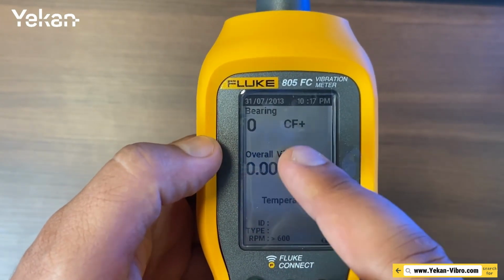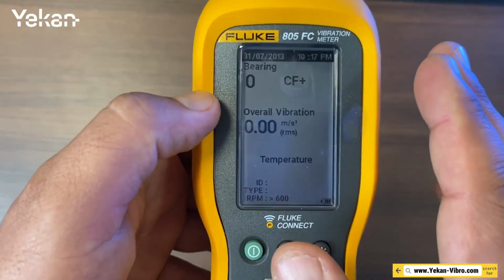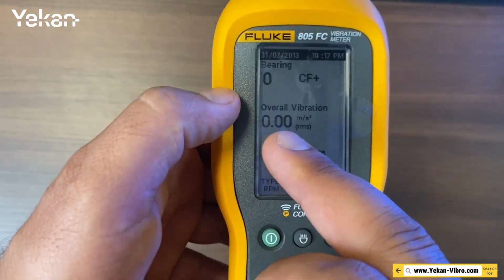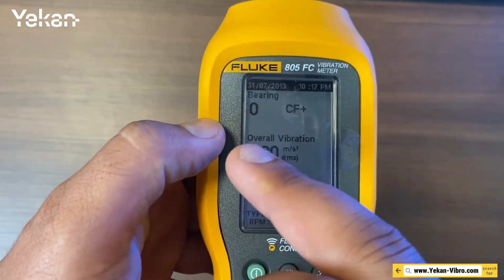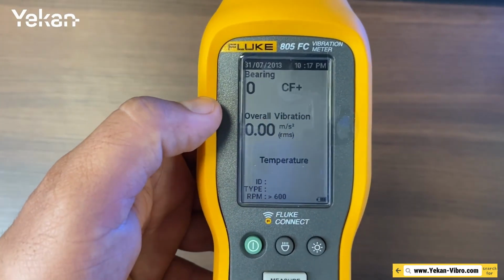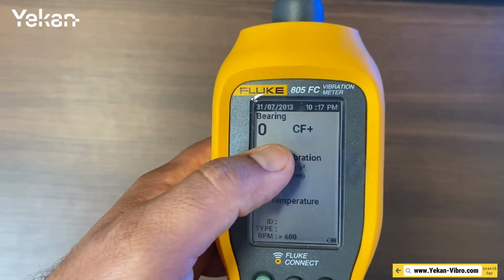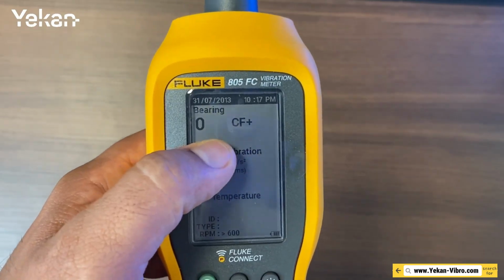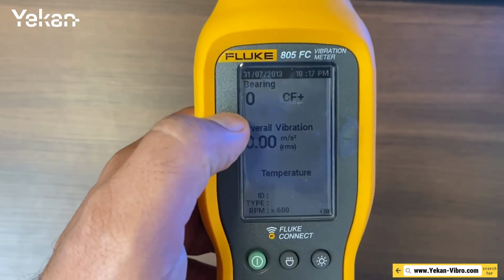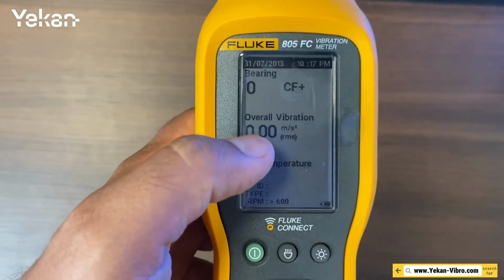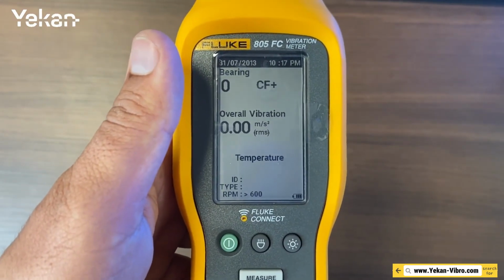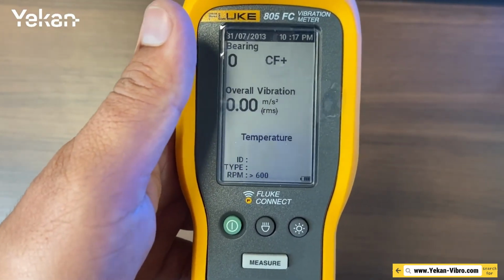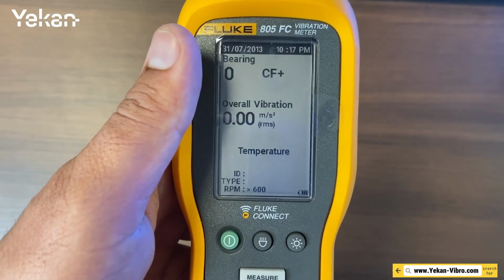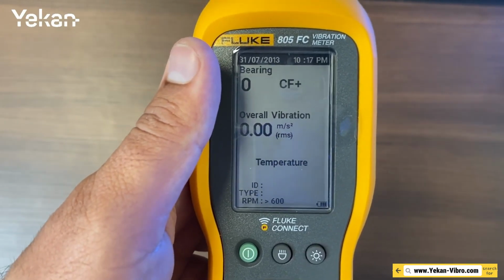Based on ISO standards and the type of machine you define here, along with the measured overall vibration, it shows you the bearing condition according to the standard. I cannot say for sure whether that data is fully valid or not. Personally, I prefer to read the overall data myself and, based on the conditions, decide at what vibration level it should be considered an alarm or a danger level.